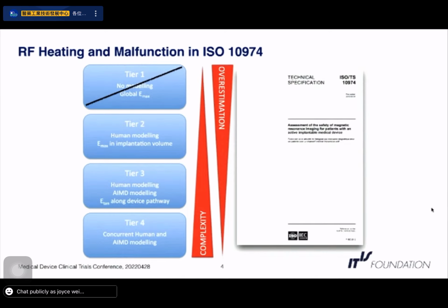a 4-tier approach. Although the new edition that's in review at the moment will remove the first tier. And it's important to know here that the lower the tier number, the less complex the model needs to be, but at the same time, the more we overestimate the deposited power caused by this implant. And the further we go towards a higher tier number, the less is the overestimation of the deposited power, which opens up the possible MR scans to a wider range of the population, but it's also connected to more complex models that are necessary. And the IM analytics is mostly used for the tier 3 assessment.